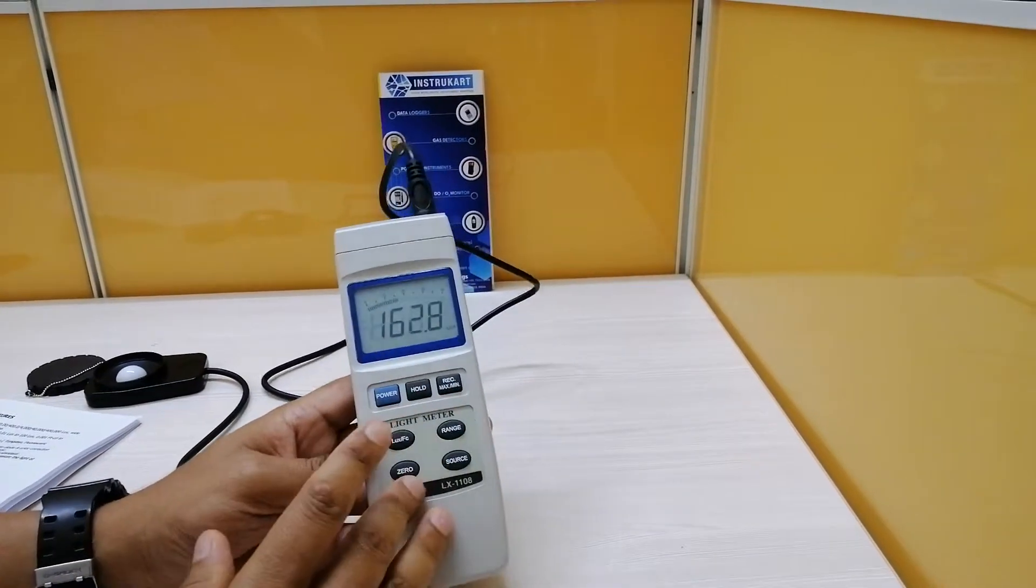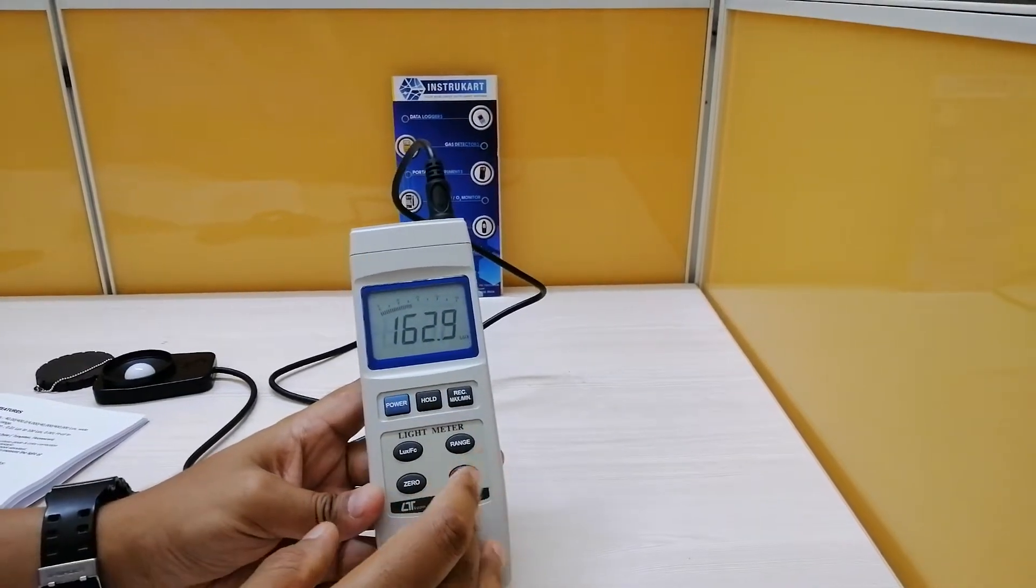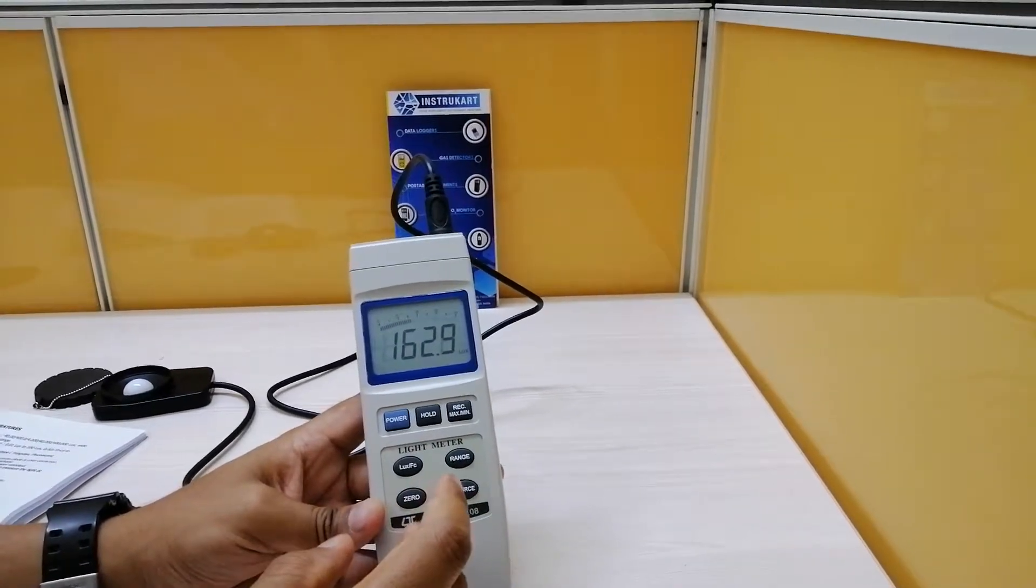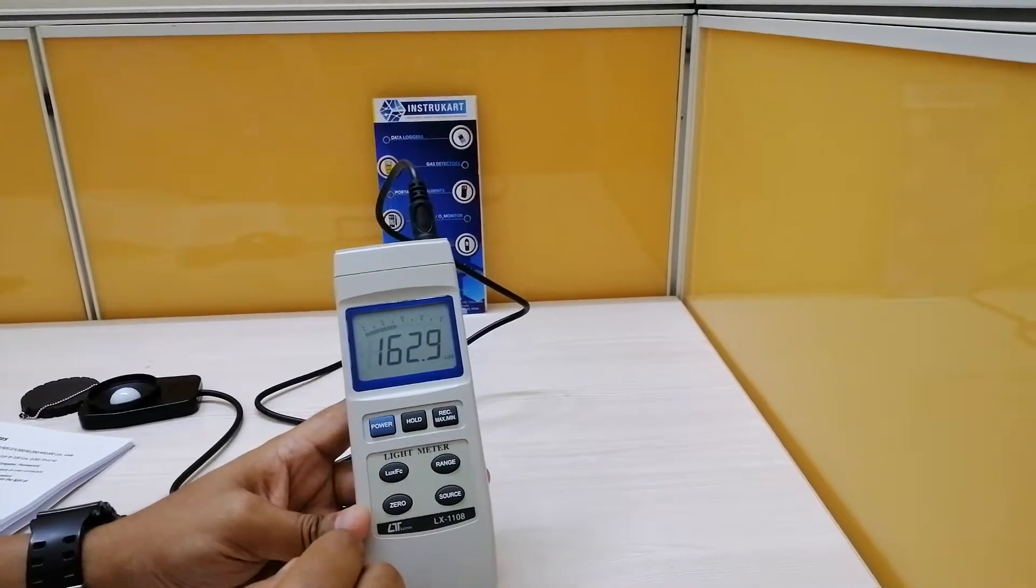There are certain keys which you can use to hold or record the lux, or toggle between lux and foot candle. You can also set it to zero or use the range or source button.